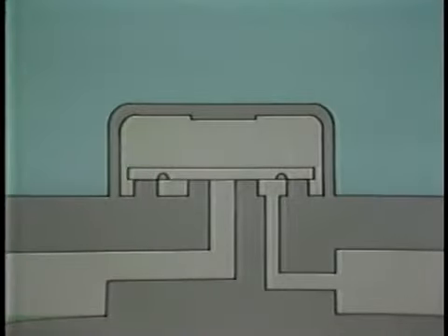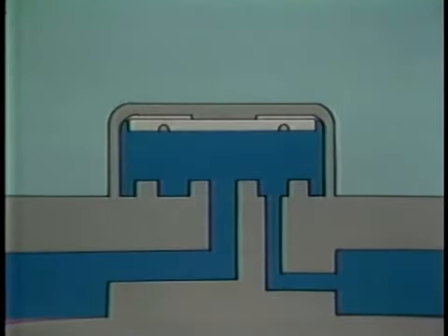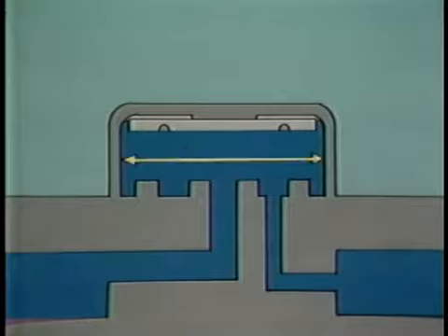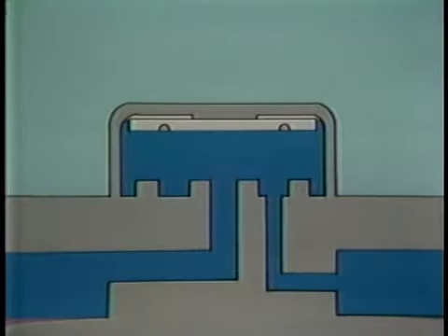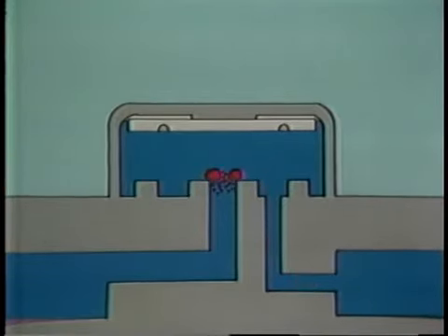On startup, condensate at the inlet port pushes the disk off the seat and flows freely to the outlet port. Condensate passing into the trap drops in pressure. If the condensate temperature is sufficiently high to have reached the saturation for this reduced pressure, some of the condensate re-evaporates or flashes back into steam. Since steam occupies a much greater volume than condensate, flow velocity increases between the disk and seat, resulting in a pressure reduction in this area.